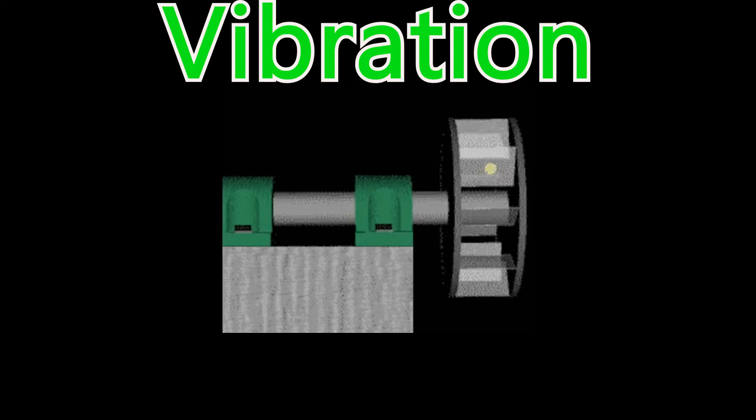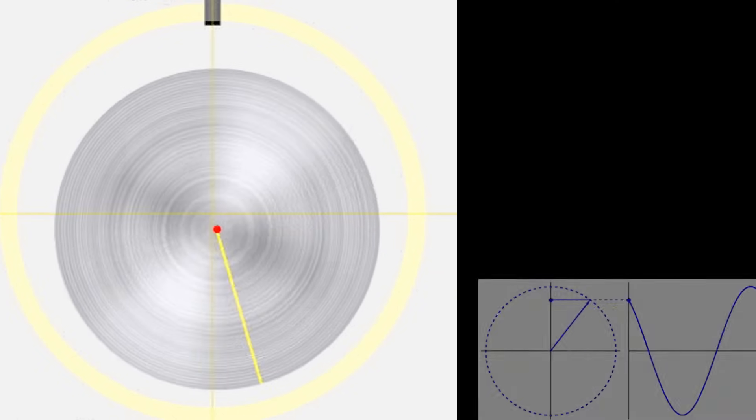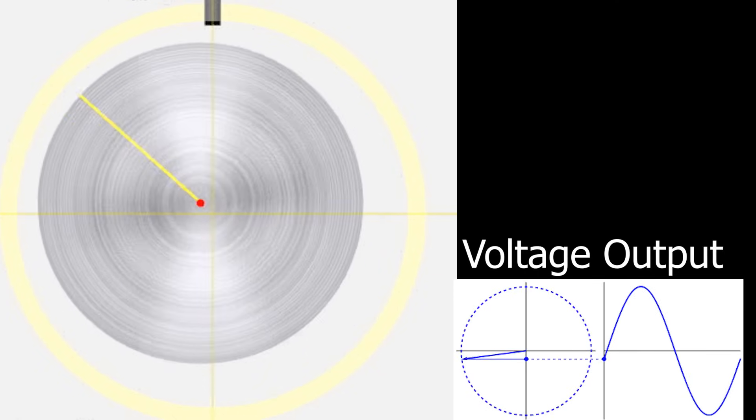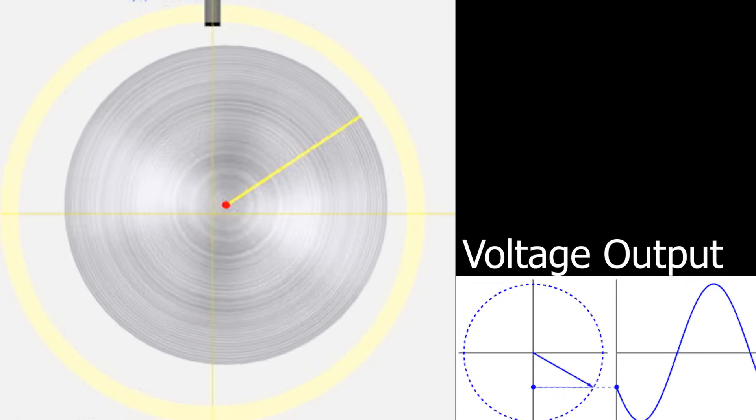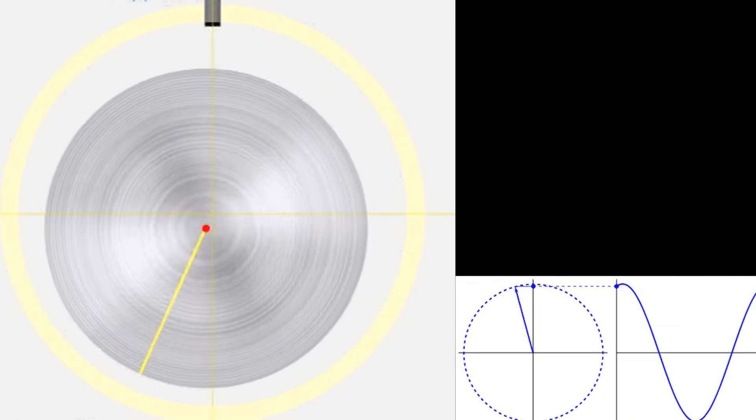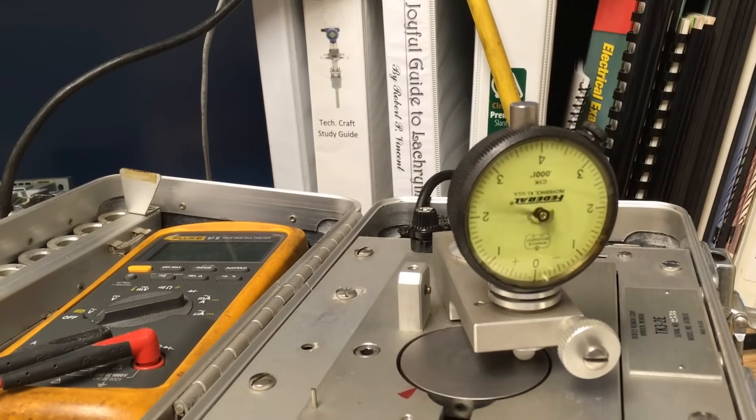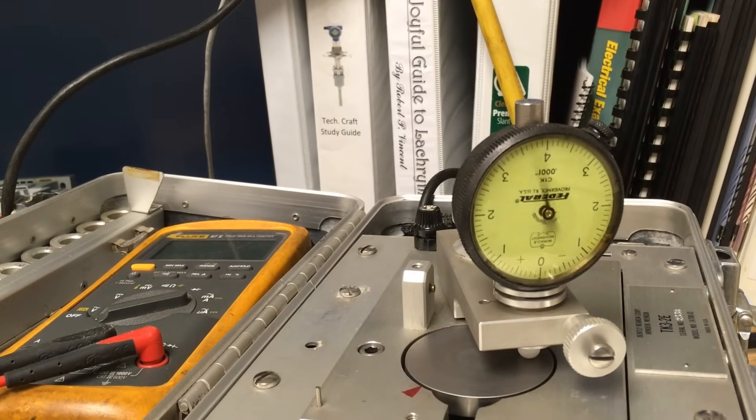If you want to measure vibration, the DC gap voltage will not work. When vibration occurs, the voltage will begin to oscillate as the distance between the probe and the shaft changes. If you notice on this demonstration, this vibration simulator machine is producing a 10 mil oscillation.